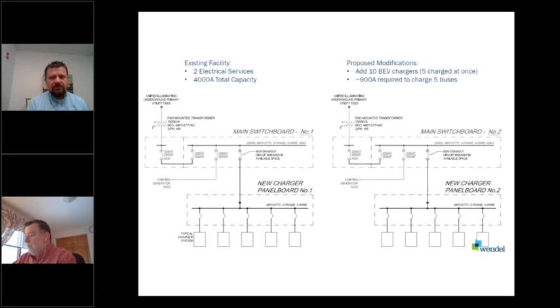As John mentioned, we were also tasked with analyzing 100% fleet electrification. The next slide shows how the distribution system has to grow to accommodate that much charging equipment, and how physical equipment would need to be added. The total load would be about 10,800 amps of charging at a time. The following slide shows a planning diagram we use when recommending or starting design of electrification projects.